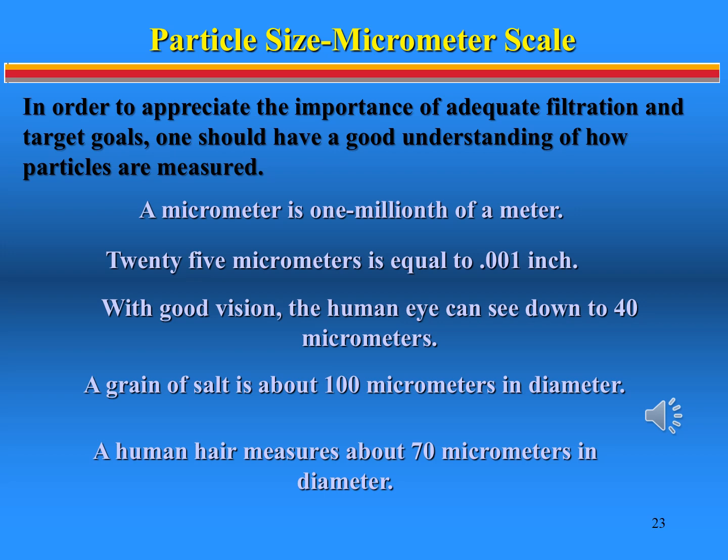Anyone involved with the service and maintenance of hydraulic equipment should be familiar with measurement systems used to identify particles by their size. The common units used are microns. 1 micron measures 39 millionths of an inch.